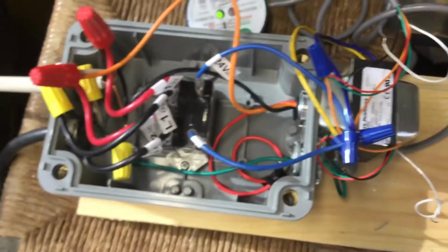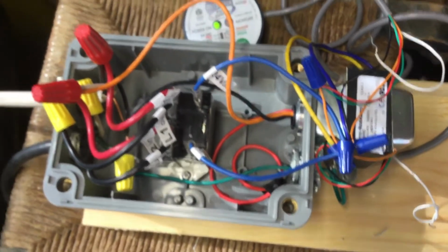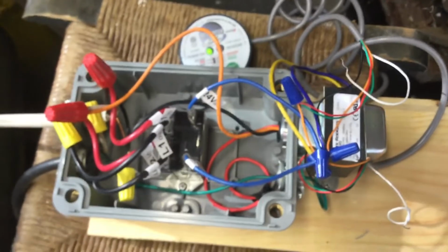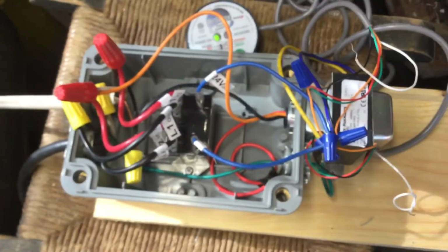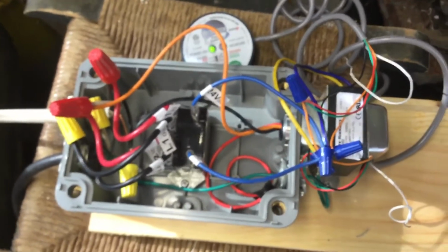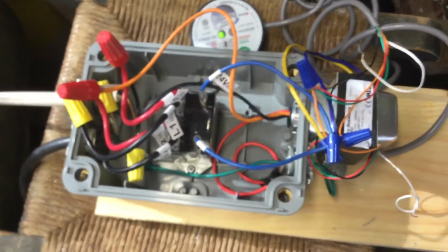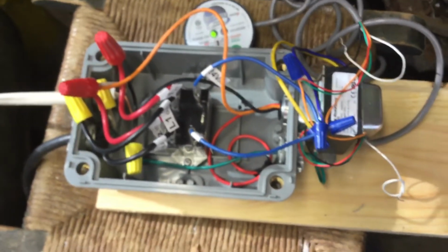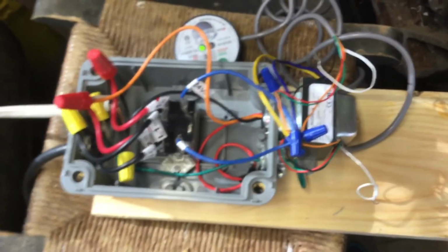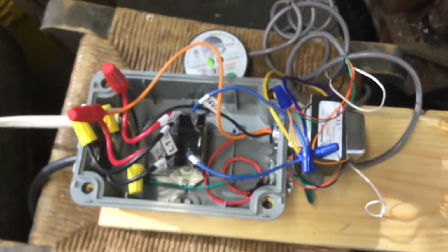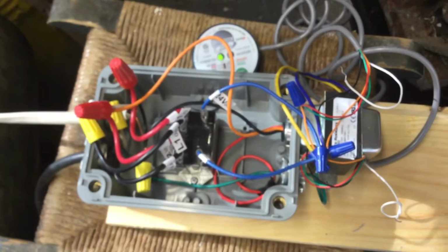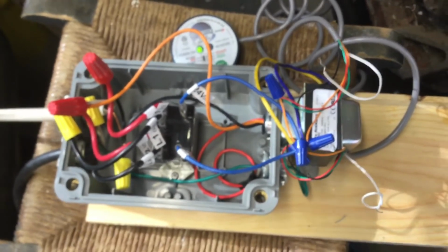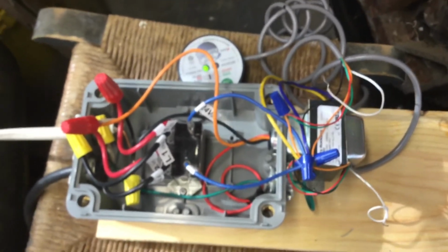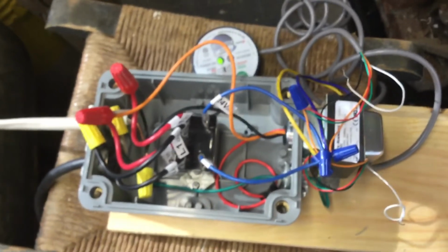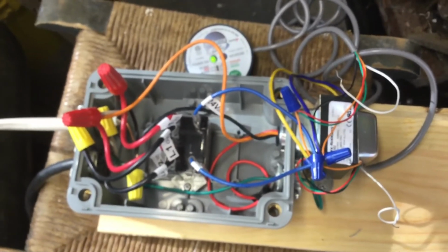you're going to find out you don't have any water in your house. And also the geothermal units have a default: if they don't get water going to them, then they automatically lock out and shut off. So that way the system is pretty much safe. If it happens at night when you're sleeping, or if you're gone away for a couple days or even a day, I mean, the well pump puts out 33 gallons a minute. In 8 hours time, that puts out a lot of water to flood everything under the house.